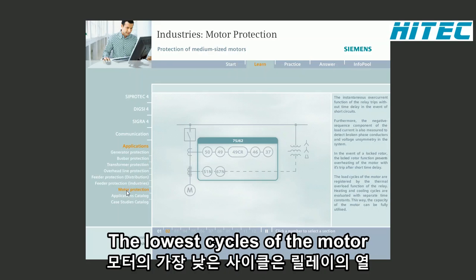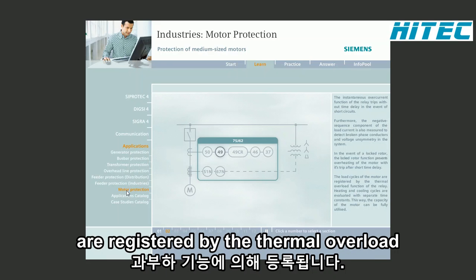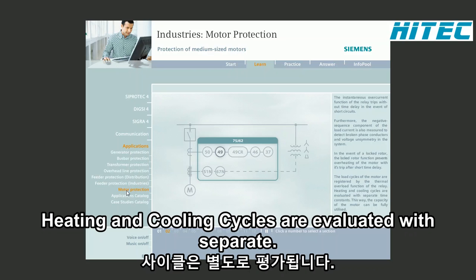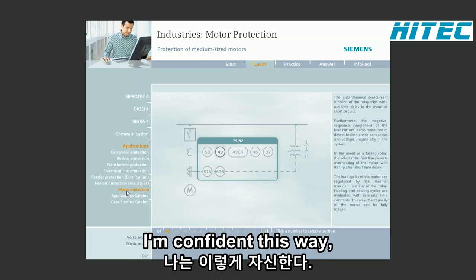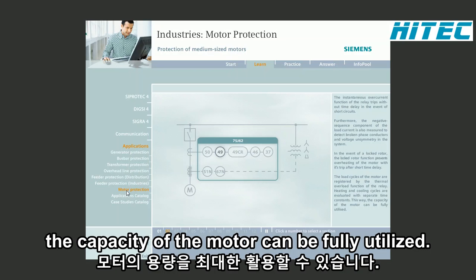The load cycles of the motor are registered by the thermal overload function of the relay. Heating and cooling cycles are evaluated with separate time constants. This way, the capacity of the motor can be fully utilized.